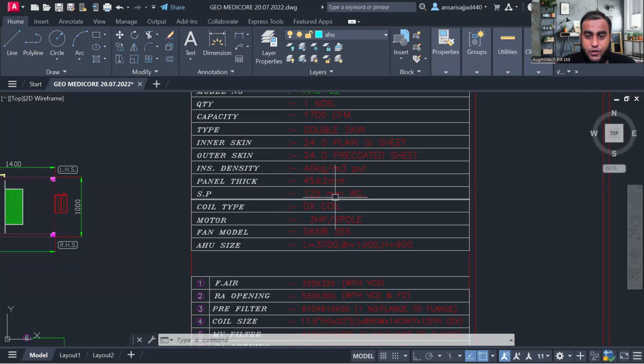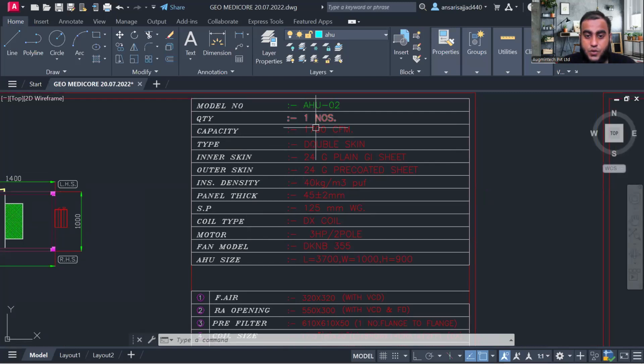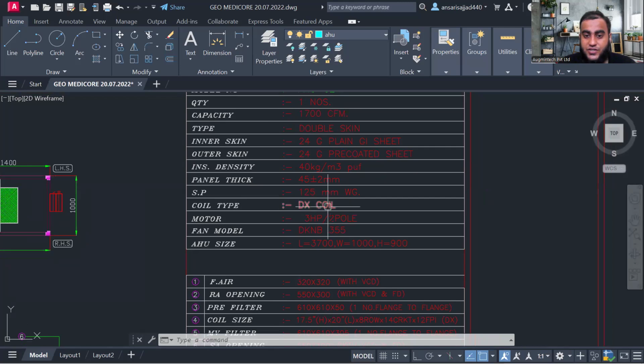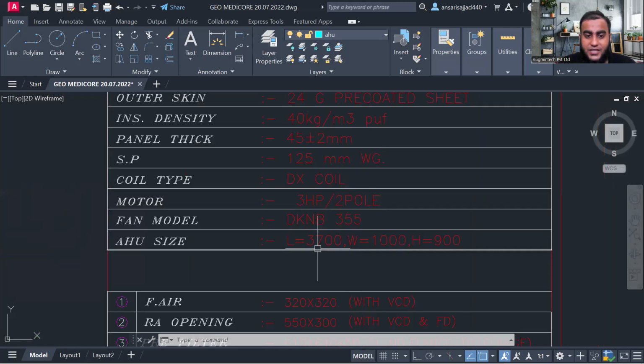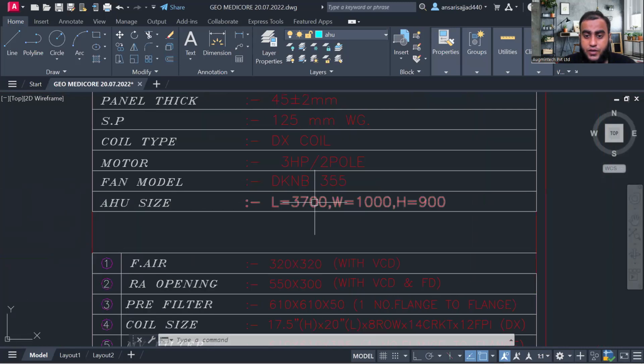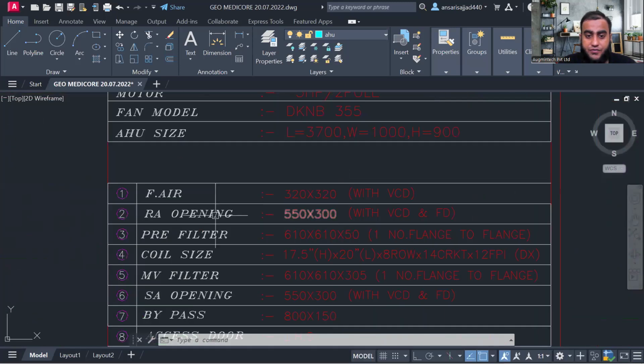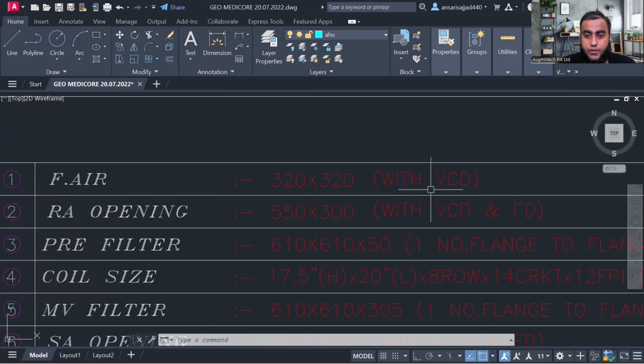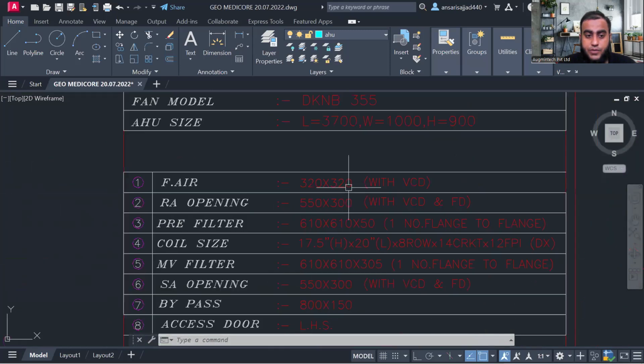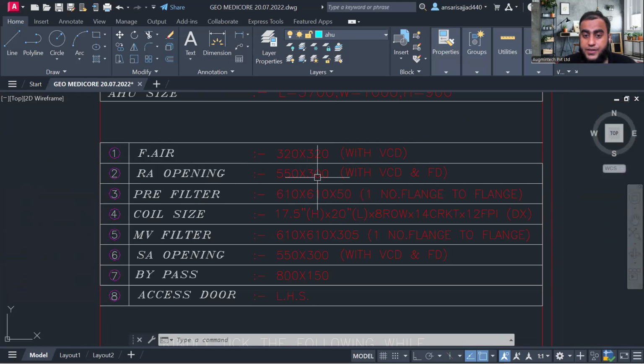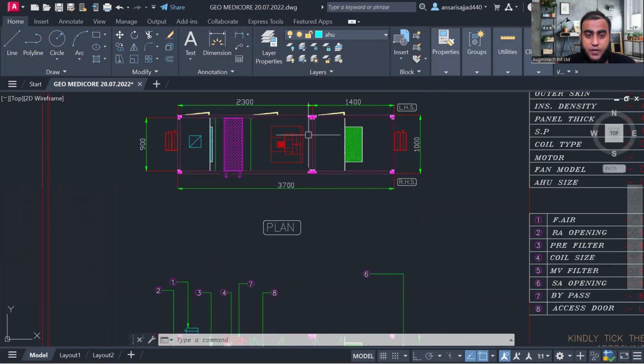Even the static pressure value, see, that is why I am telling you about static pressure, and all these values you have to see. Coil type, DX or chilled water, motor, 3 HP motor, fan model is given here, AHU sizing is given, total length, width, height. Even you can see the fresh air opening size is also given with a volume control damper, 320 by 320 mm. Return air opening size is also given, as are pre-filter size, coil size, MV filter size, supply air opening size, bypass, access door. You can see this is the plan view.